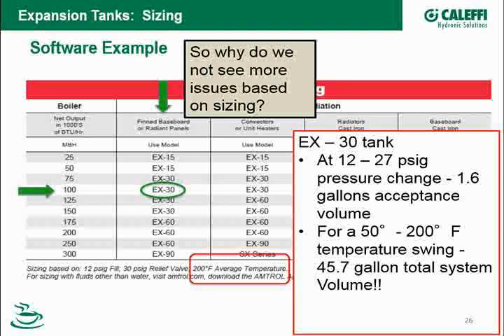Oh, absolutely. Even, if you look at this here, back to your point, if somebody's doing any kind of buffer tank, whether it's 60 gallons, 75 gallons, or 119 gallons, they definitely shouldn't work off of the chart. I would go back and do a calculation off of one of the design software on one of the manufacturers' websites, because you're certainly above that 45.7 gallon total volume size.